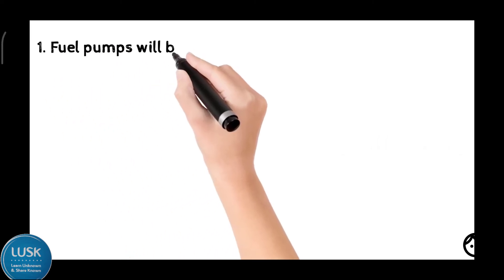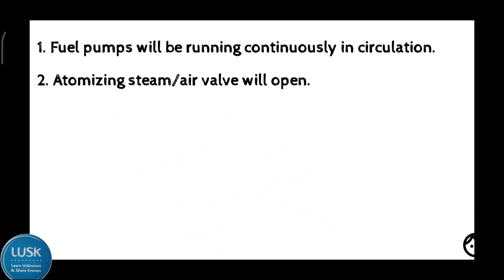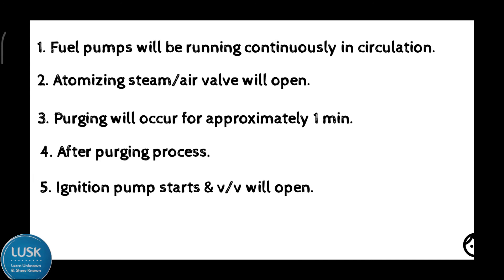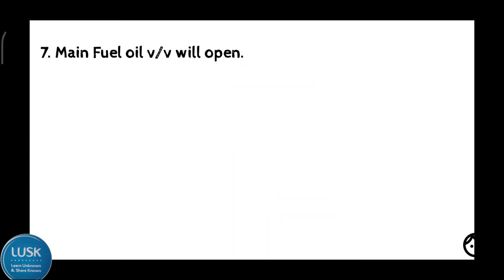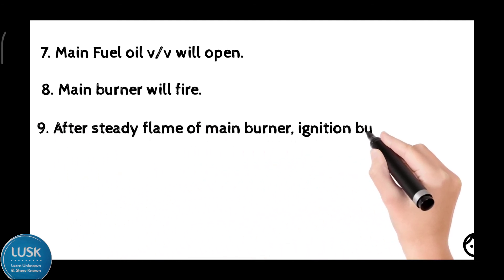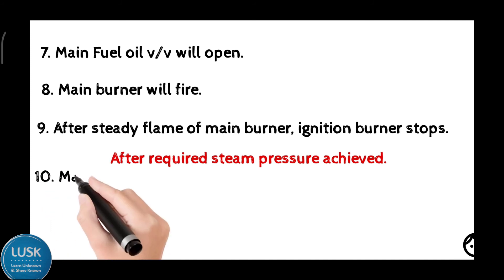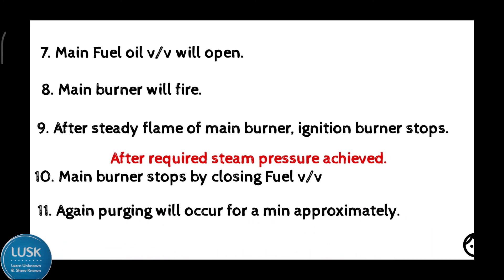Let's see the boiler firing sequence in a very fast manner. First, fuel oil pumps will be running continuously. Then atomizing steam valve will open, or compressed air valve will open for atomizing. Then purging will happen for one minute. After purging period completes, ignition burner pump will start and those two valves will open. Then pilot burner will start firing. Then there will be a flame sensor that will detect there is a flame inside the burner. Then main fuel oil valve will open. Then main burner will start firing because of the pilot burner, and the flame sensor will detect. Then as soon as there is a steady flame, ignition burner will stop. Then after achieving the required steam pressure, main burner will stop by closing the fuel valve, and purging will occur.